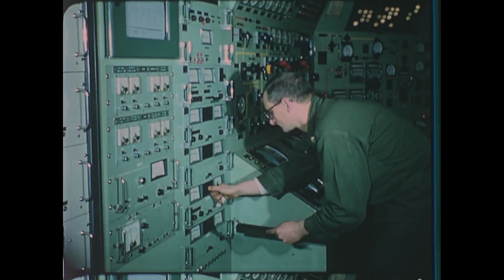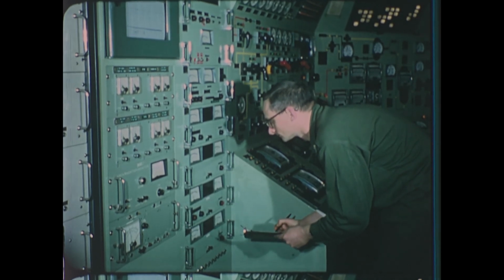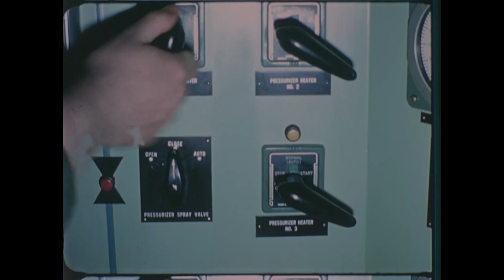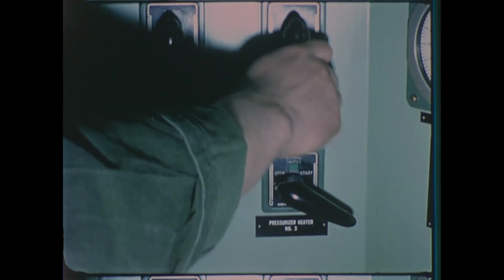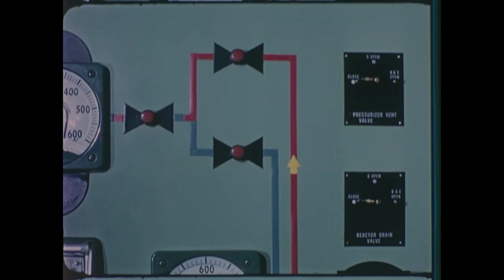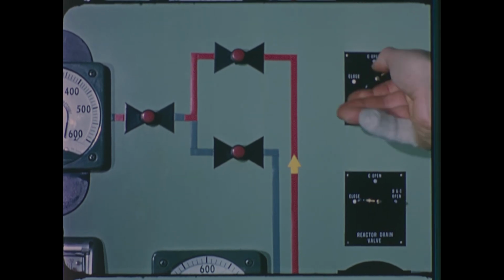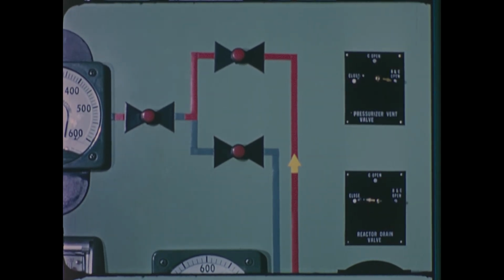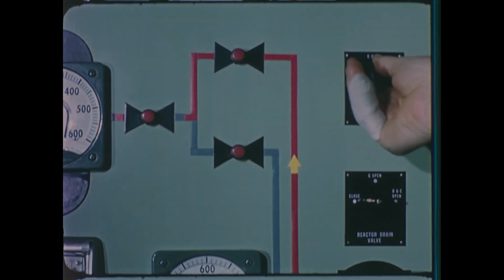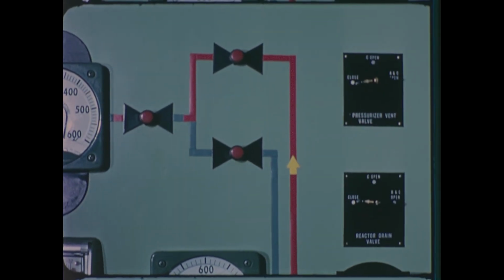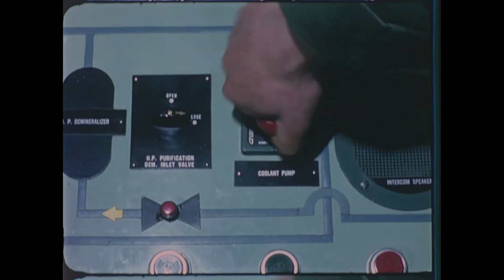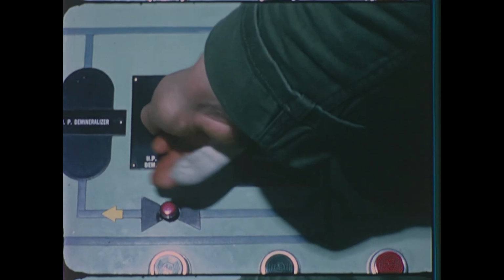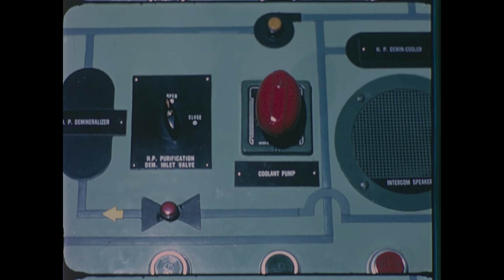There, with the primary system solid and free of air, he energizes pressurizer heaters to establish pressure in the system. The vent and drain valves provide a means to vent the pressurizer to the expansion tank in order to relieve pressure in the system. Starting the primary coolant pump and opening the high-pressure demineralizer isolation valve puts the purification system in service.